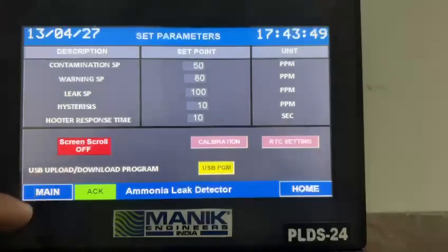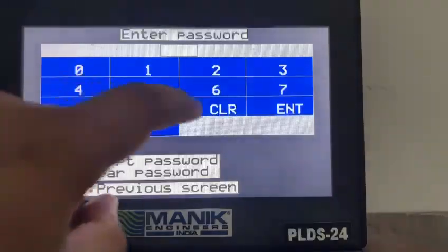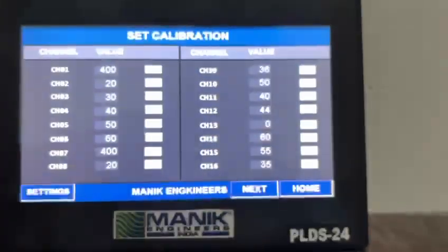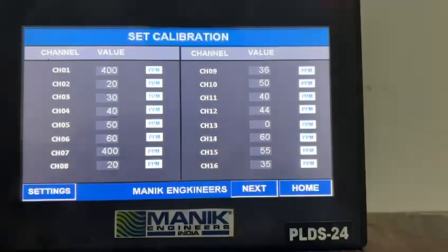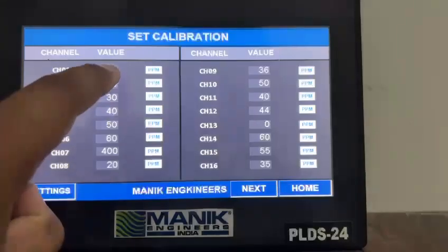At the bottom side, the screen scrolls, and calibration and RTC settings buttons are available for their operation. Calibration helps to correct small deflections in readings to minimize the wire losses. So touch on the calibration button here and enter the password. Once the calibration screen is visible, we have channel number 1 to 16 visible to set the calibration value. Just touch on the calibration keypad to set the calibration value.